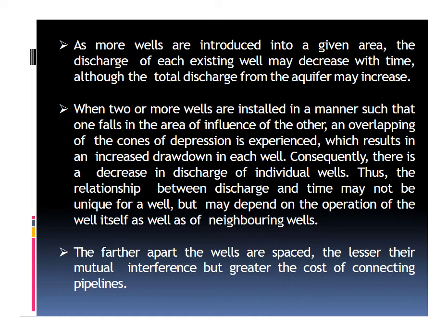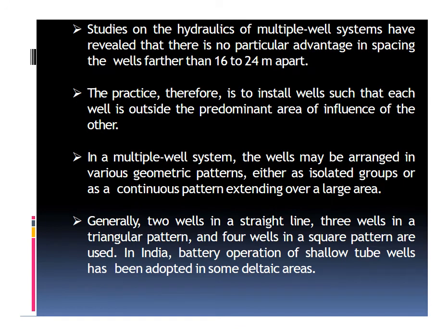The farther apart the wells are spaced, the lesser their mutual interference, but greater the cost of connecting pipelines. Studies on the hydraulics of multiple well systems have revealed that there is no particular advantage in spacing the wells farther than 16 to 24 meters apart.